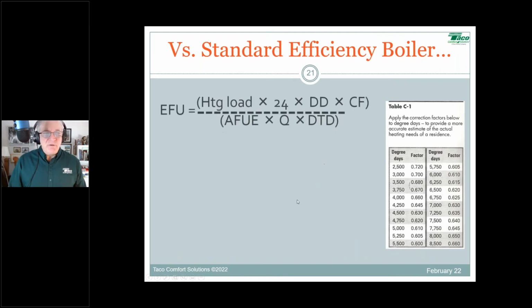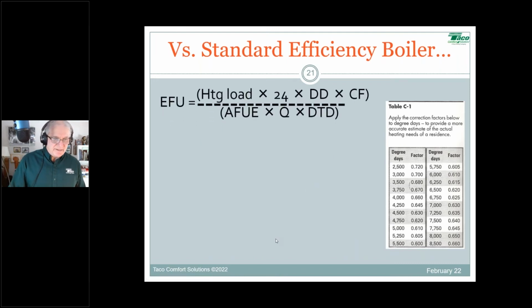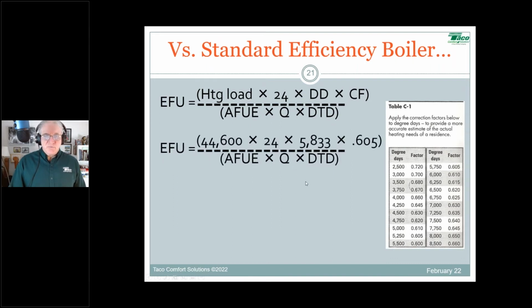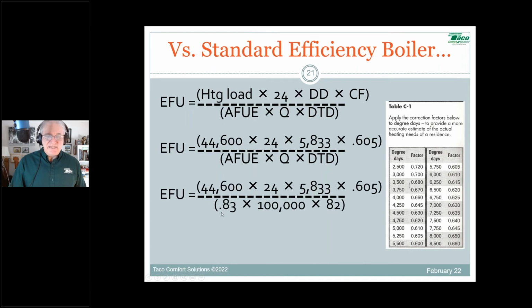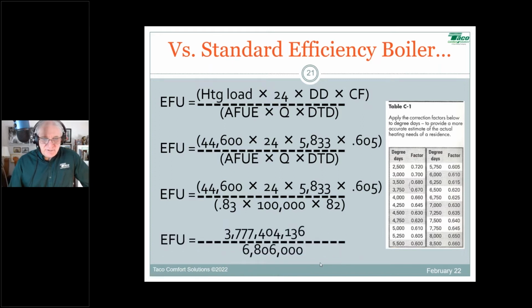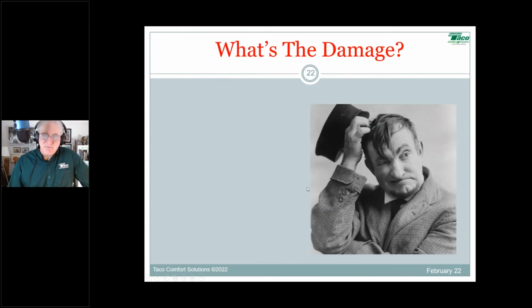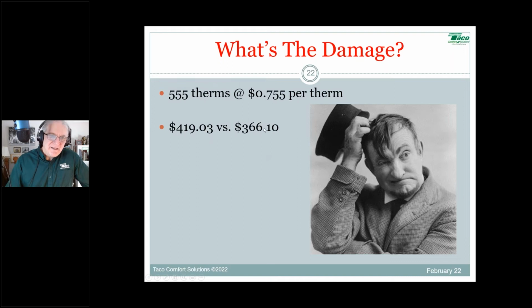All right, now again, if we were to compare this to a standard efficiency boiler, as we talked about, compare the whole thing to a standard efficiency boiler. We have all of the same information in, but let's put in an 83% efficient boiler compared to the 95%. You can do this math with any number that you want, but let's say a standard efficiency, 83% cast iron boiler. We're going to look at the numbers a little bit, and the numbers might be surprising. That's 555 therms. So we're talking 419 versus 366. So that's 53 bucks for the year.